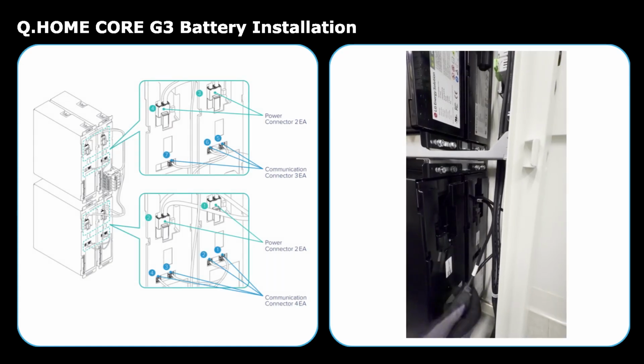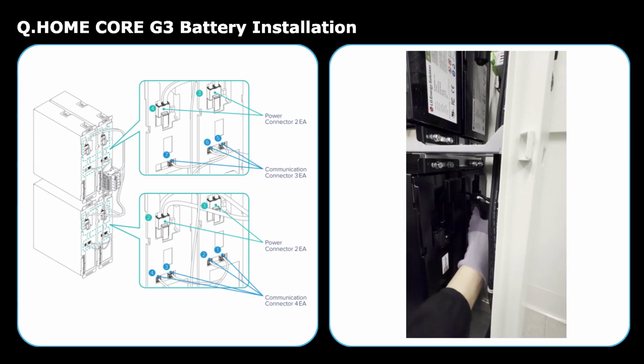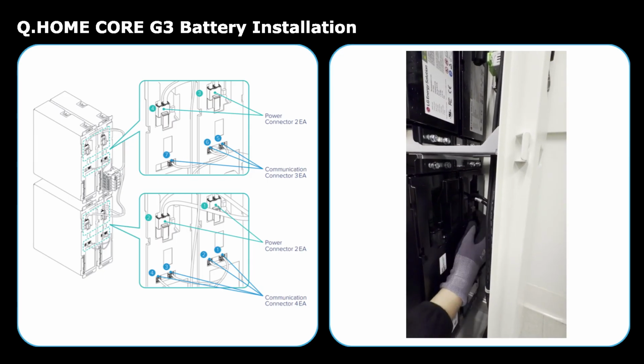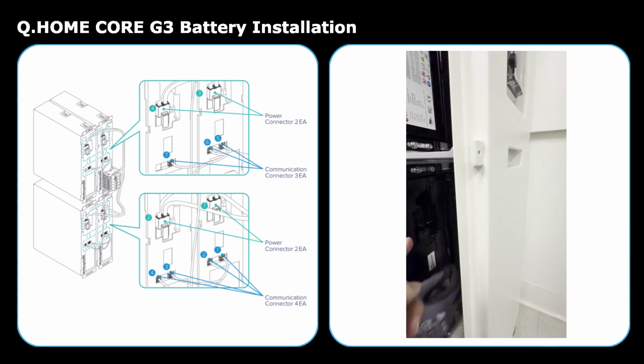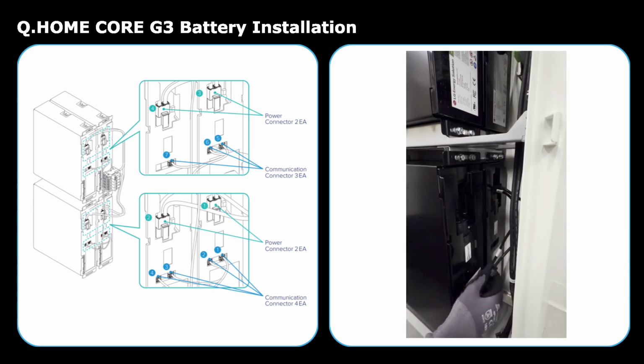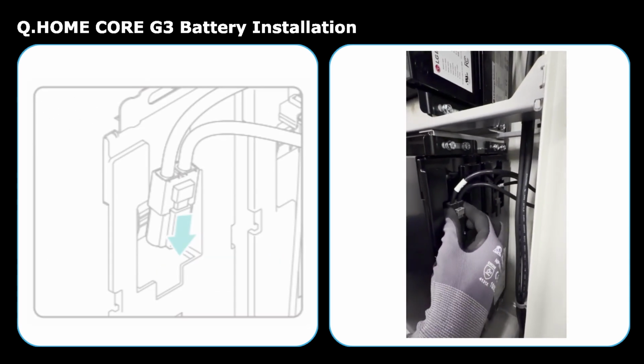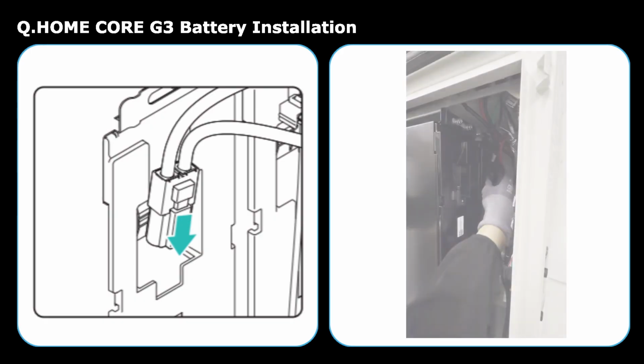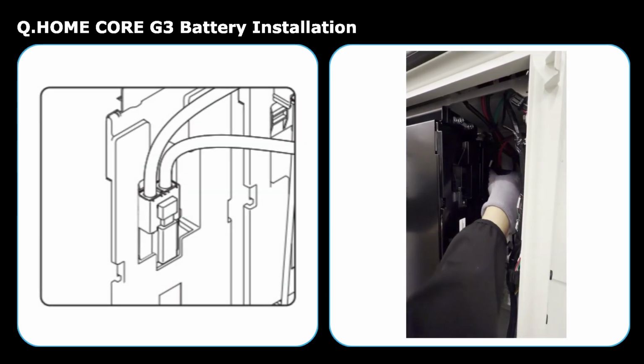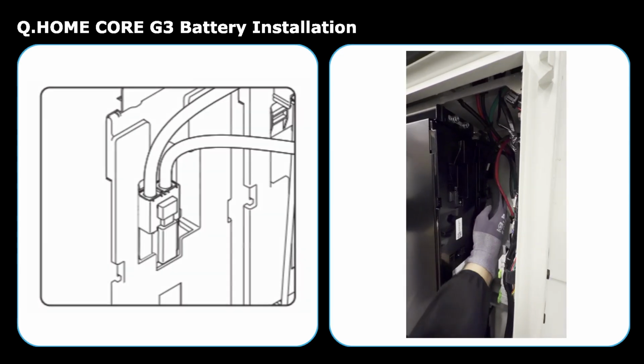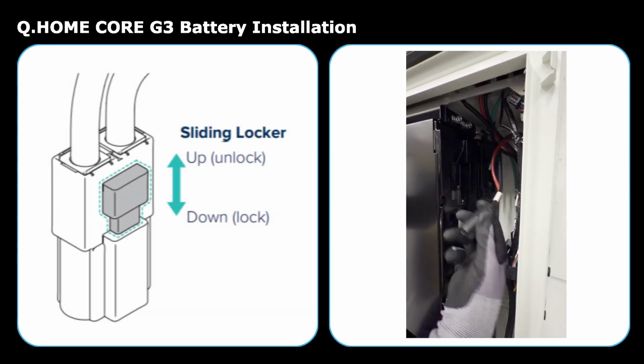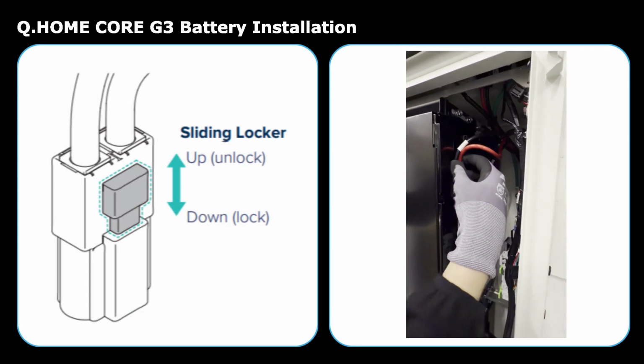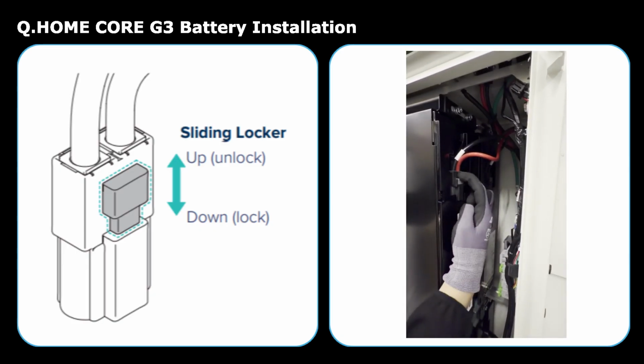Please connect the cables in this order: bottom inner battery first, bottom outer battery second, top inner battery third, and top outer battery last. Each connector is keyed. Push until you hear a click, then gently pull to verify the cable is securely locked. Remember, incorrect cable connections can lead to installation errors and communication faults.